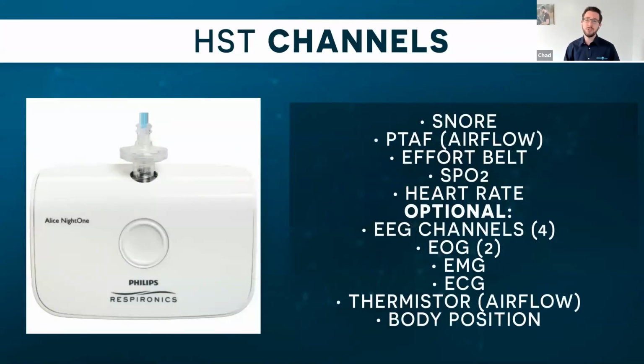When it comes to an HST, they have to have 4 required channels for them to be considered a diagnosable HST. They must have snore, airflow, effort belts, and pulse oximetry. Those are required. A unit like this one on the left-hand side will also have positional data and have some adaptations to be able to look at a couple different things. Alice NightOne is just 1 unit, not an endorsement, just a unit that's available in the marketplace. So it has a couple extra little pieces that are available.